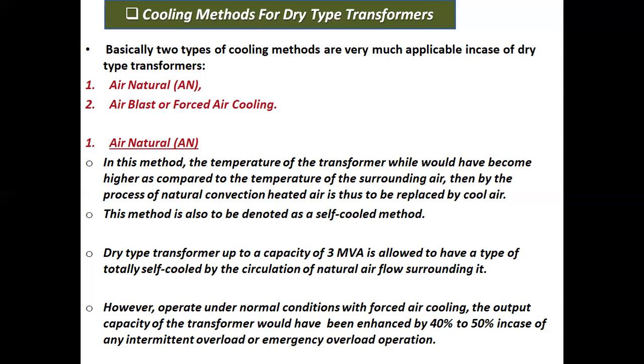Dry type transformer up to a capacity of 3 MVA is allowed to be totally self-cooled by the circulation of natural airflow surrounding it. However, when operated under normal conditions with forced air cooling, the output capacity of the transformer would be enhanced by 40% to 50% in case of any intermittent overload or emergency overload operation.